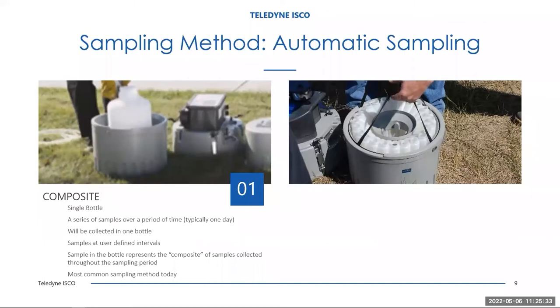For automated sampling — and these are portable samplers — for pathogen sampling, typically one would use a single bottle. A series of samples will be collected over a period of time, typically one day. Oftentimes that pacing will be time-paced where a sample is collected every 15 minutes throughout the full 24 hours. Samples are collected at user-defined intervals. The sample in the bottle represents the composite of all the flow that moved past that location over that sampling period — that 24-hour day. This is the most common sampling method used for this purpose.